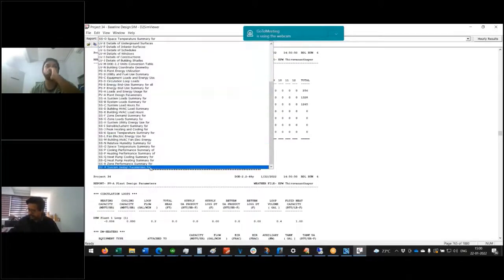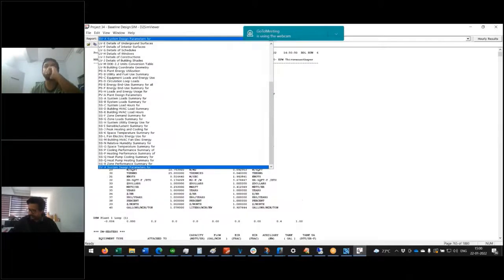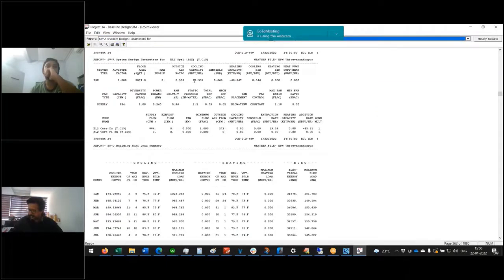So which clearly indicates that the air conditioning system is not fully capable, even though it is sized for the peak load. But when it can remove only our sizing, you see, is 29 kBtu, as we saw, TC15, 29 kBtu. So cooling capacity is 29 kBtu per hour. So every hour it can remove only 29. But imagine that from the morning itself, almost 10 kBtu keeps getting added, and the first hour 10 kBtu it handles well because peak is this. But then what is happening is, as you go later towards the day and towards the night, that heat is being added up, and it is significantly greater than what this cooling coil or capacity can handle.